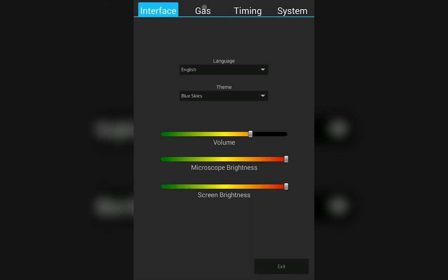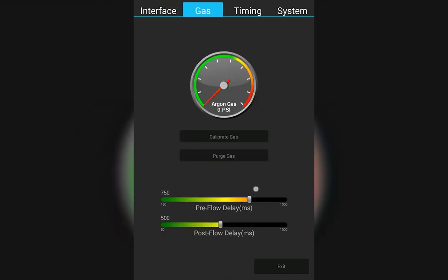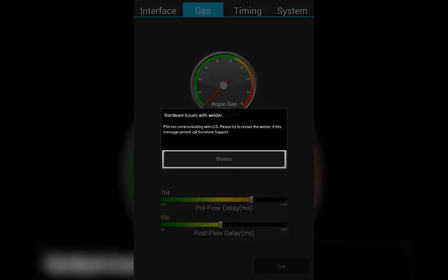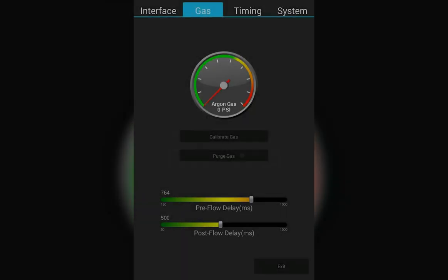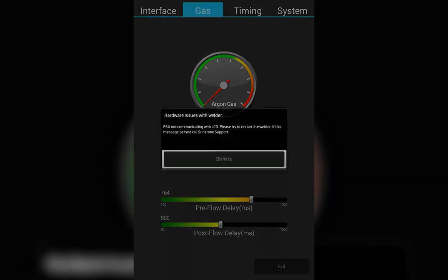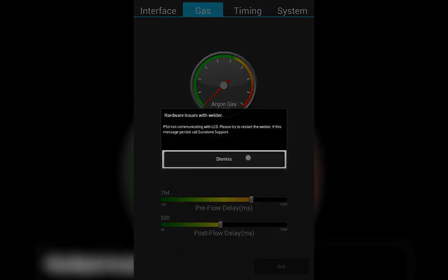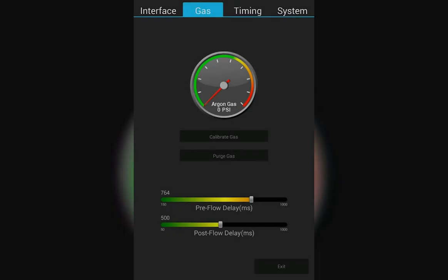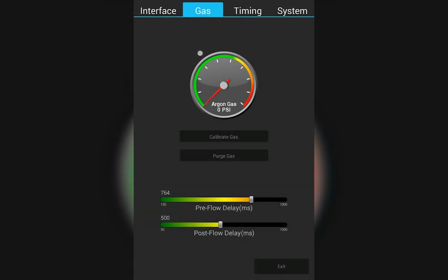On the gas tab, you have the option to adjust your pre and post flow delays. You also have the option to calibrate the gas and to purge the gas. Once connected to an argon gas tank supply, the gauge here will give you a readout of the pressure that you have coming into the machine.